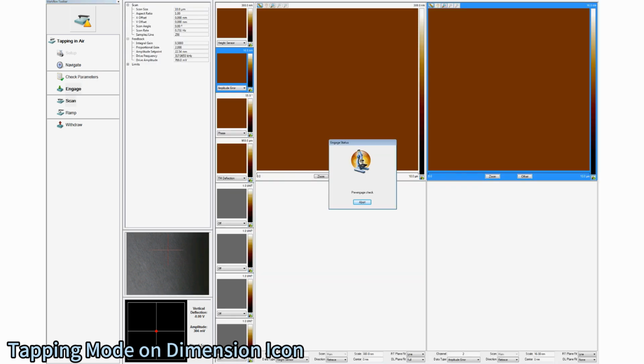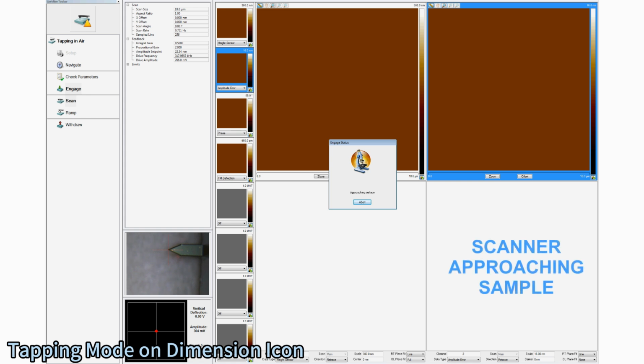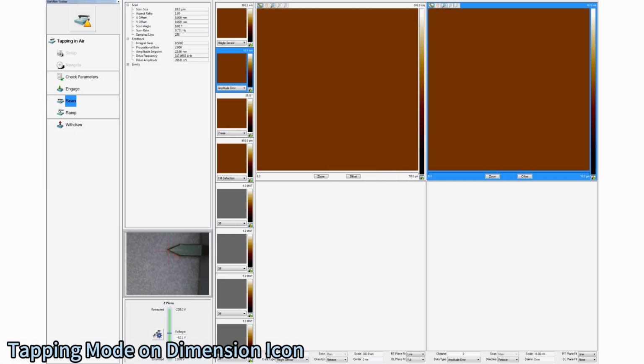The approach process begins by shifting the focus to the probe and lowering the Z-stage motor until the probe encounters the force region above the sample. The Z motor slows down and the piezo begins stretching downward until the probe achieves the amplitude set point value. At this point, the Z motor stops and the feedback loop takes over the control of the piezo and probe position, while monitoring and maintaining the set point resonance amplitude.